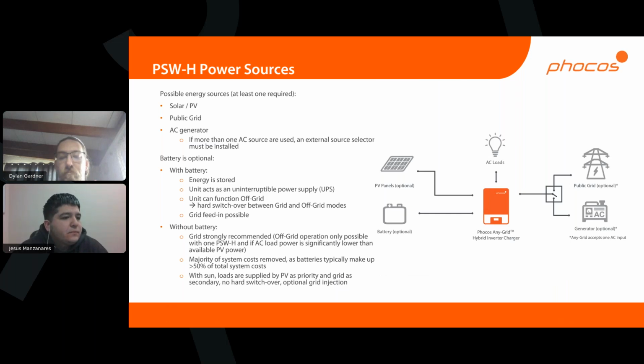Yeah, we do have a question here. Can you use the 230 volt for split phase instead of getting two? Dylan, do you have any? Yeah, so if you have 240 volt loads only, then that works fine. It can be set to 60 hertz or 50 hertz. But just keep in mind, there's no center tap on that unit. This device is a single phase output per unit. So even to get split phase, like 120, 240, you need two units to produce that.